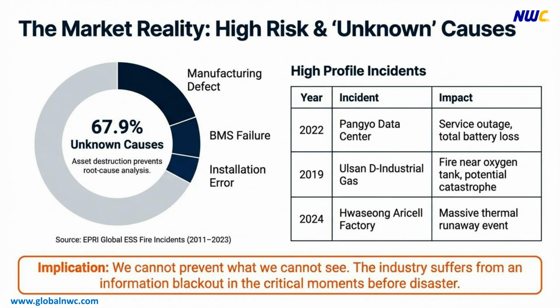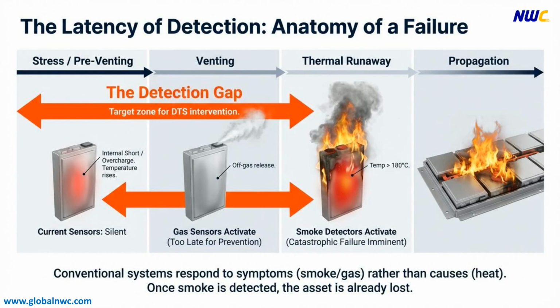This is why the industry urgently needs data-driven, innovative solutions capable of providing visibility into the critical moments just before a disaster occurs. Conventional gas and smoke sensors typically activate only after off-gas release or thermal runaway has already begun, making them insufficient to prevent significant asset loss. As illustrated here, the detection gap, from the battery stress stage to just before thermal runaway, represents the critical golden time where early intervention through DTS technology becomes essential.